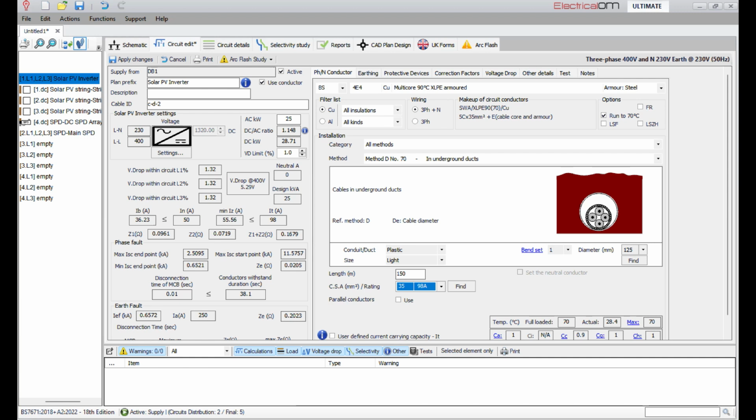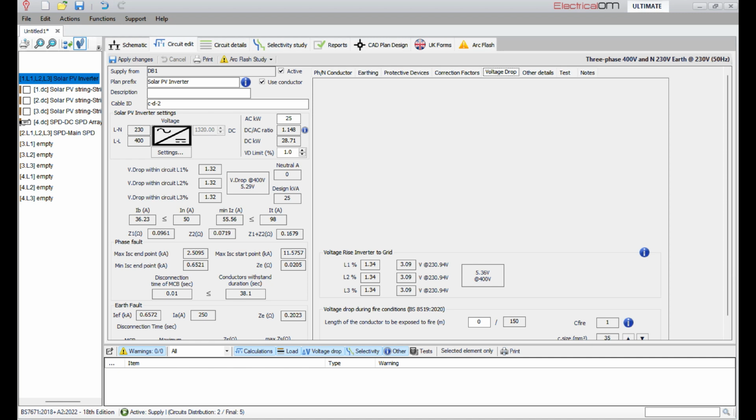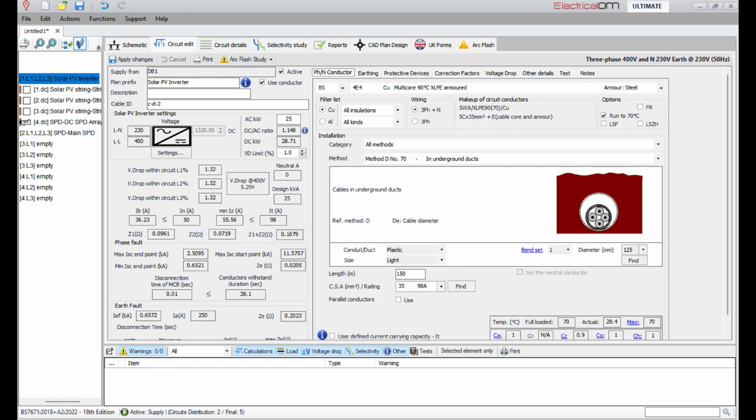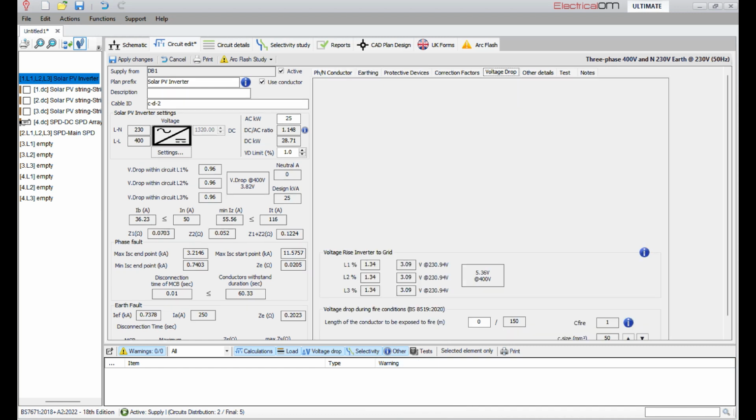So it's an indication of what's going on as you change your cable size, because volt drop's the enemy when you've got long cable runs, along with your earth fault loop impedance values. And you can see there we've got 1.34% of volt drop on the PV inverter with those 35 mil conductors.